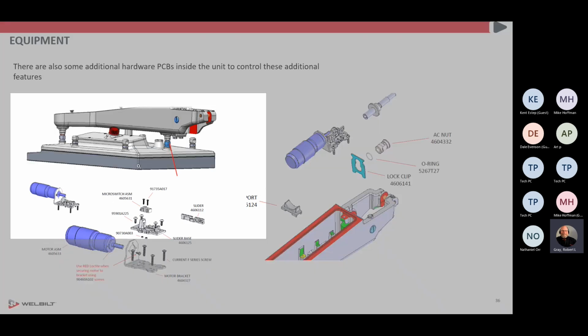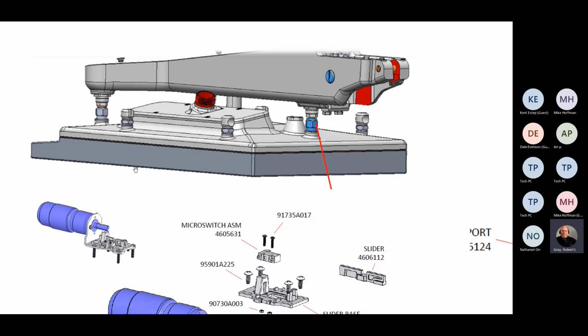Also, what's different here, if you have experience with the clamshell grills on the next generation platform, you know Chick-fil-A has the platen hangers in reverse. You know that McDonald's has a motor in here to adjust the rear. And we also know Chick-fil-A has 2 adjusting bolts. Wendy's in the General Market Express Grill, you have 3 adjusting shoulder bolts. Okay, adjusting nuts. Looking at this picture right here, you see that the blue highlighted nut here is the actual nut that attaches through the cowl. That's this part here at the top of the platen and into the platen itself.